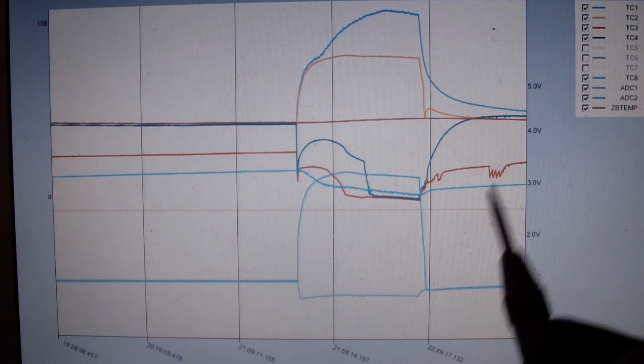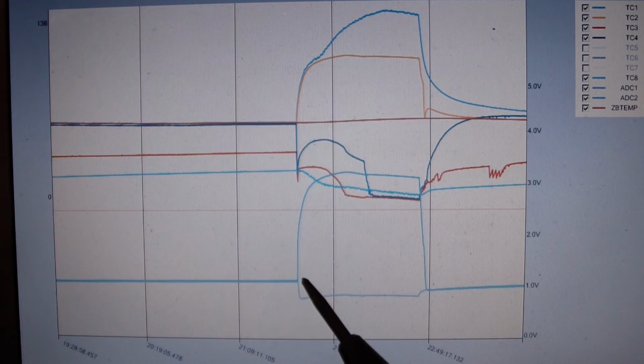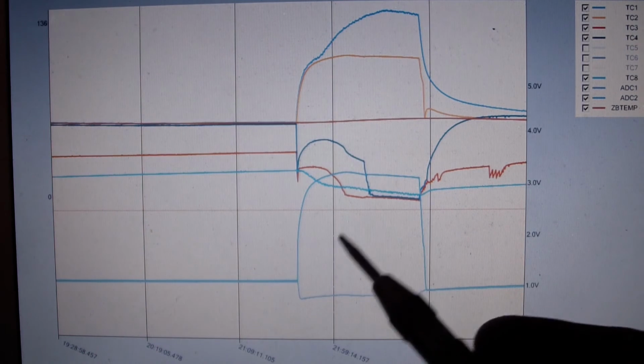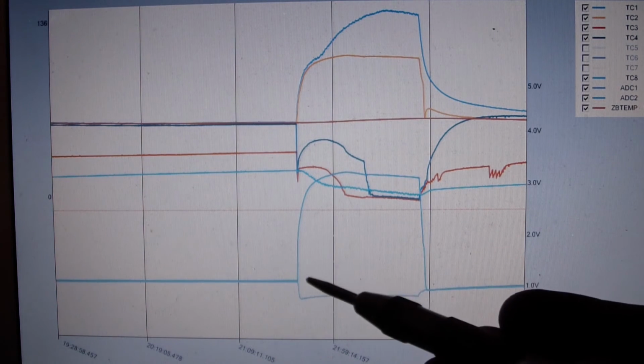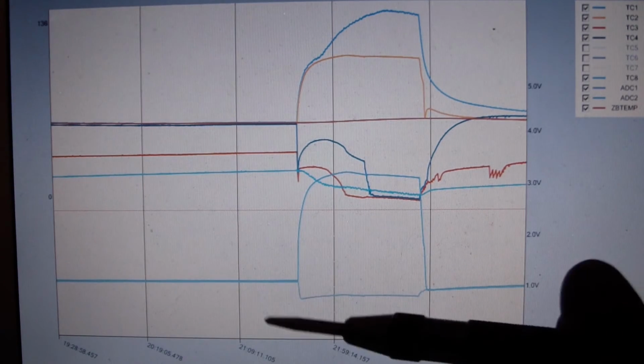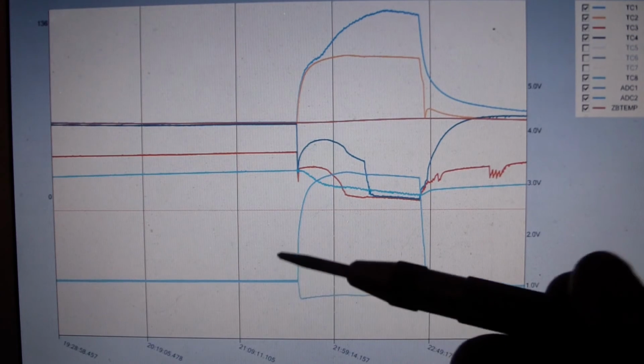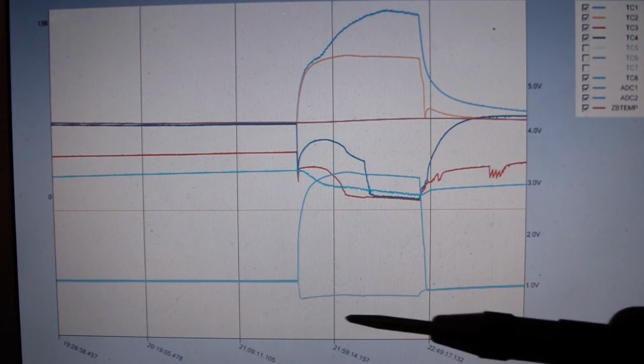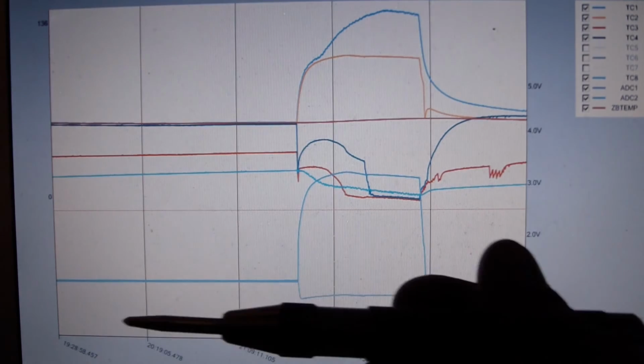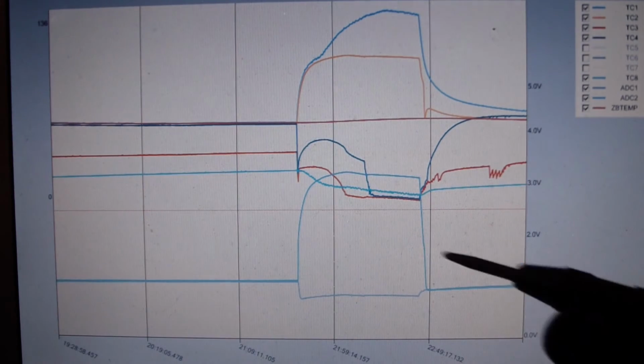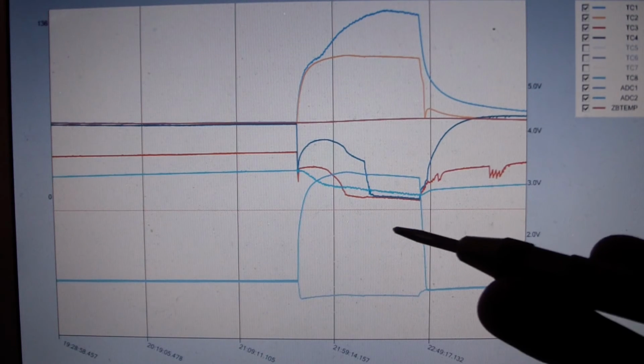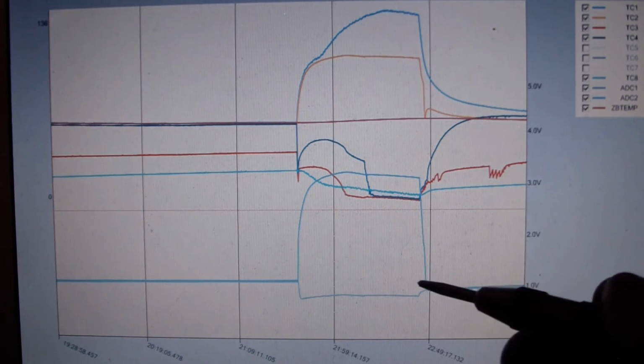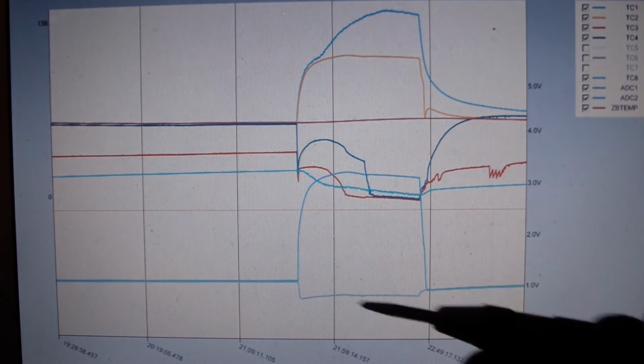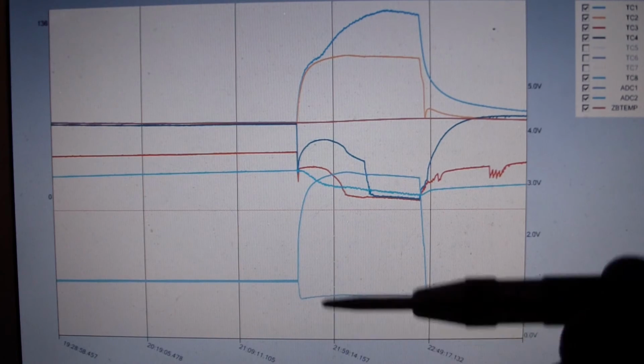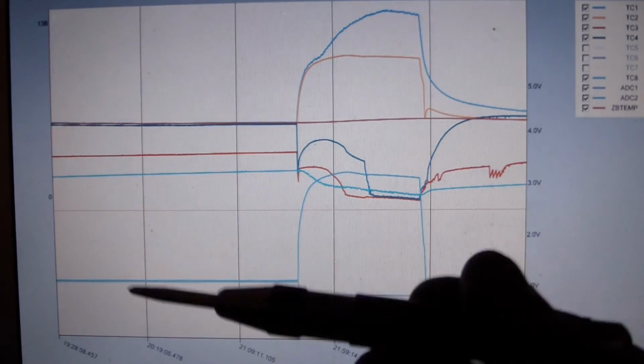So say for instance in low ambient conditions, the head pressure is going to have to build and build and develop a pretty hefty liquid plug behind the capillary tube until the pressure rises enough that it's really effectively condensing liquid. So you're going to have liquid backing up into the high side. And conversely, in really high ambient conditions, when it's rather hot, the high side pressure is going to be pretty high anyway, and it's really going to be rocketing a lot of refrigerant through to the low side. So the point I'm trying to make is you need to have some place for that liquid to go, and that's a tank of some sort, a receiver.